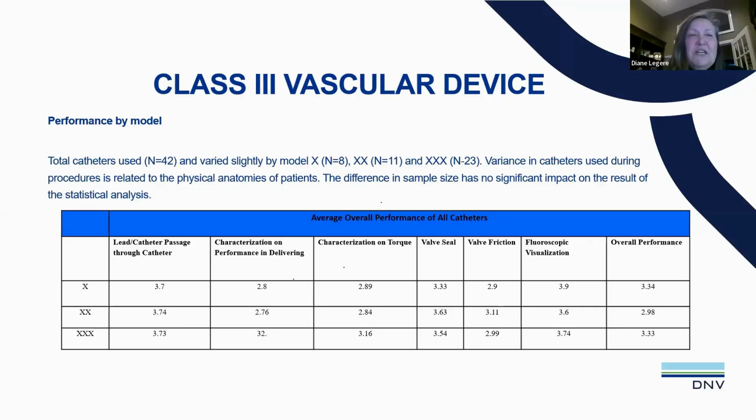Okay. So here's an example from me, and I think it is similar to your class 3, that even though it's a class 3 device, like my example here, it delivers into the cardiac space. It's a guide catheter that delivers other devices. So high risk anatomy, but just because it's class 3, sometimes a simpler survey can work because, as you mentioned in your other studies, the residual risks are known.